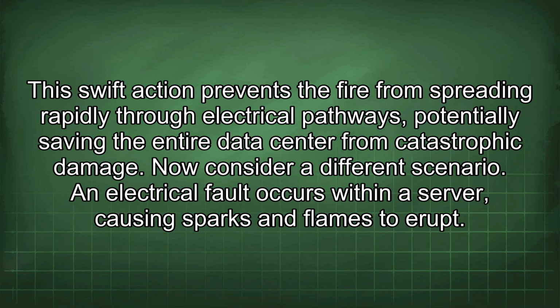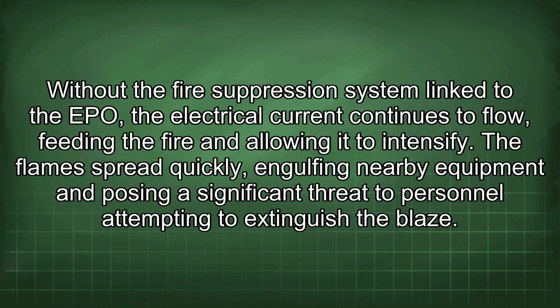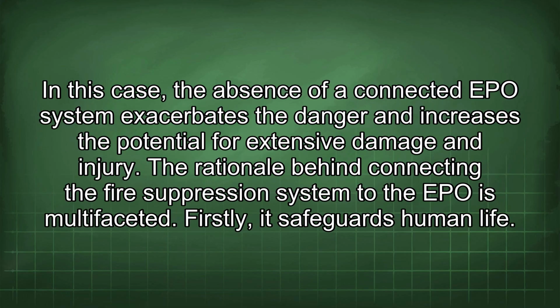An electrical fault occurs within a server, causing sparks and flames to erupt. Without the fire suppression system linked to the EPO, the electrical current continues to flow, feeding the fire and allowing it to intensify. The flames spread quickly, engulfing nearby equipment and posing a significant threat to personnel attempting to extinguish the blaze. The absence of a connected EPO system exacerbates the danger and increases the potential for extensive damage and injury.